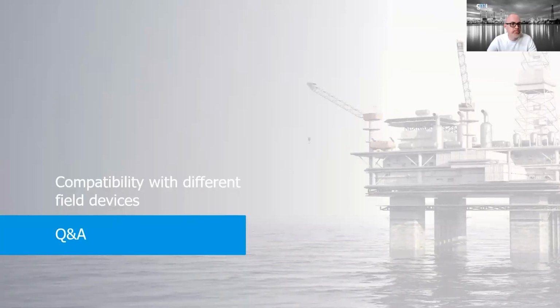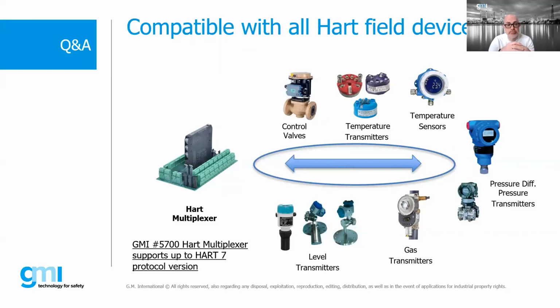Massimo? Okay, Andrea. Compatibility with different field devices. GMI's HART MUX manages devices for HART compatible analog input and analog output applications up to HART revision 7. Through HART, it's possible to carry different types of field device information that can provide information related to the first variable, which typically can be a pressure or temperature, or to sub-variables such as current or other information related to the field device.